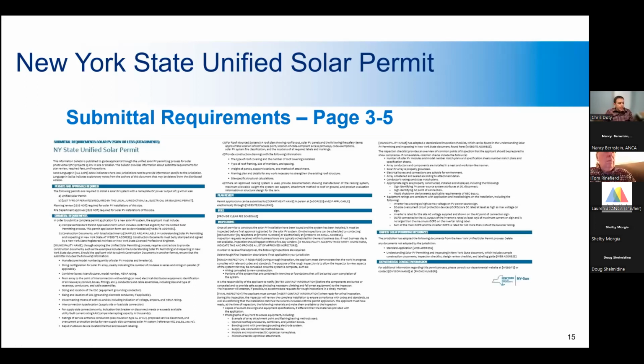All right, so now the application portion is filled out. What documents are required to accompany the application? There's 3 pages here you can see of extensive information that's required to be submitted to be compliant with New York State laws, construction documents, and other information that's critical to evaluate the system. And these requirements are basically the same for a 25 kilowatt system up to a megawatt system. Like I said, this USP is built so that it can be applied to any size system. And some of the things in here may not necessarily be applicable to each system, but you just mark those as not applicable and then move on.